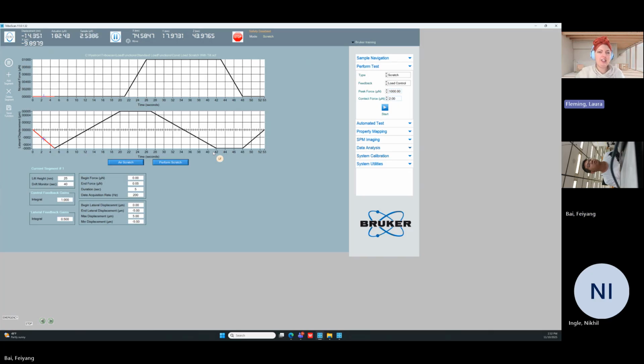I have actually run this test before, and you can see the directional dependence of a Berkovich probe depending on which way you're scratching. So your next Berkovich probe could be 30 degrees different, and all of a sudden you're getting different results. It also isn't good to blunt your Berkovich probe. If you want to do scratch testing, when you get to that point, let's have a discussion about applications and what probe you should be looking to purchase. But that's the other physical thing we should be aware of.